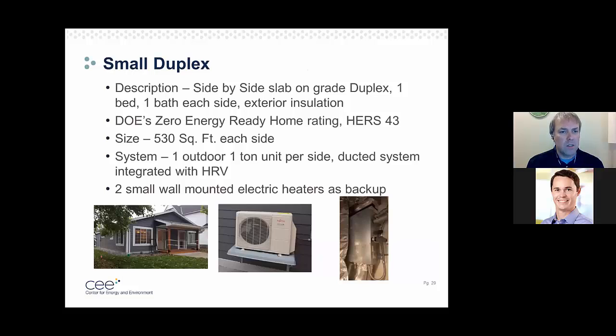The system is one outdoor unit, one ton per side, a ducted system integrated with an HRV. The ducted setup is like a mini duct system, a low flow system, very efficient and very small. It's tucked into a little mechanical closet next to the water heater, then ducted to all the rooms for heat. For backup heat, they had two small wall-mounted electric heaters.